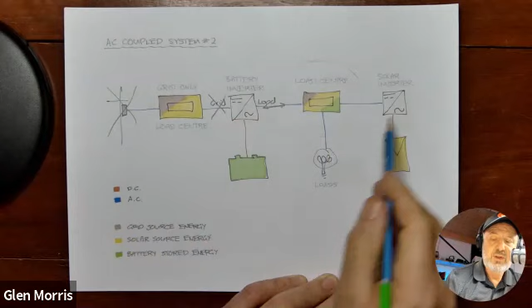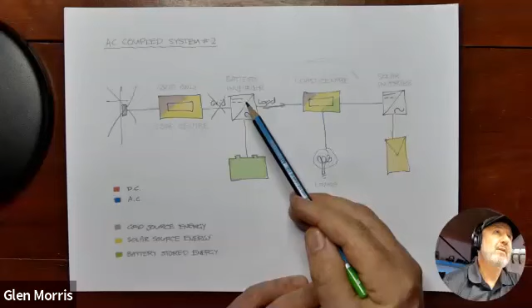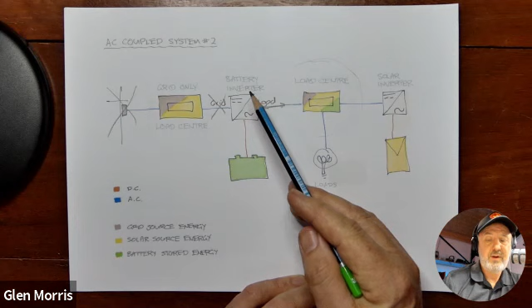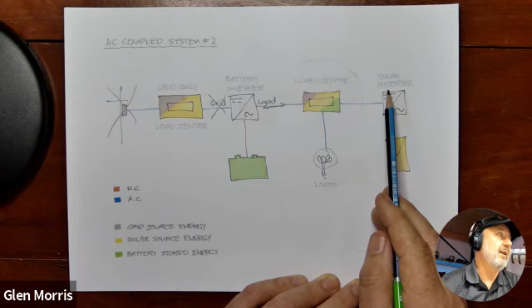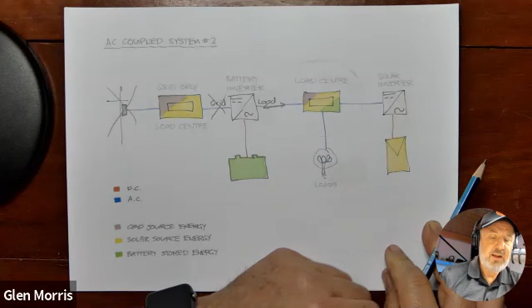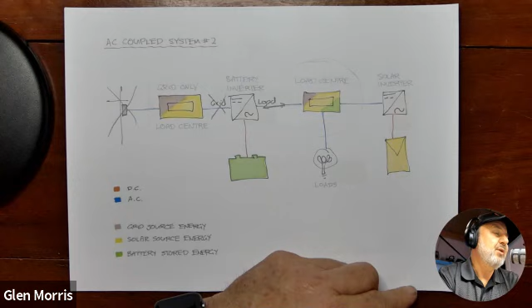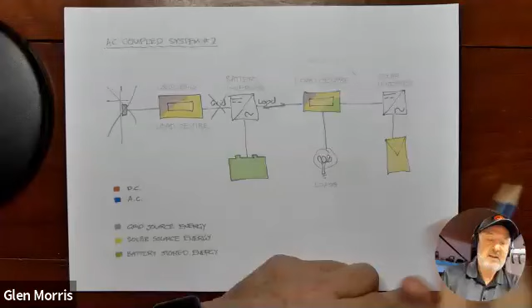Now we've put the load center in the middle here. Load center is like your switchboard, all of your home essential loads. And the advantage of this configuration compared to the other one that I just drew is that if the grid fails, we still have power. So if the grid goes off here, we still have power because the battery inverter becomes what's known as a grid-forming inverter. It actually creates a stable voltage and frequency to which the solar inverter can synchronize, and therefore everything keeps on working. So this kind of configuration allows you to have not just backup, but also backup with solar charge, even when the grid's not there. So you don't lose your solar. That's one of the big advantages.